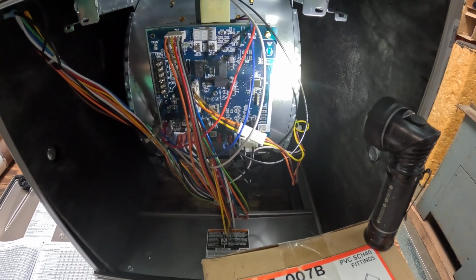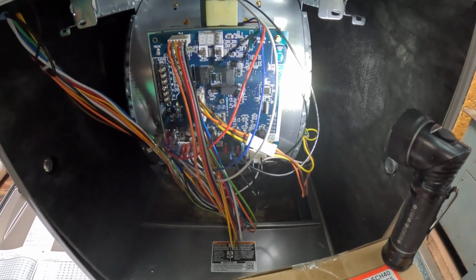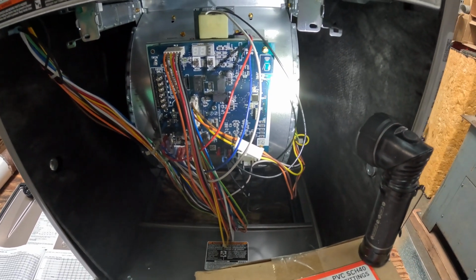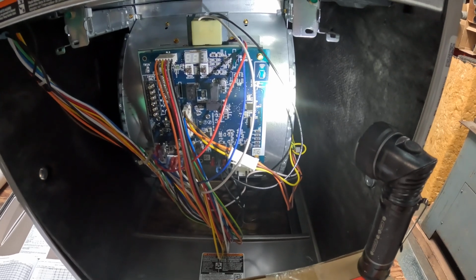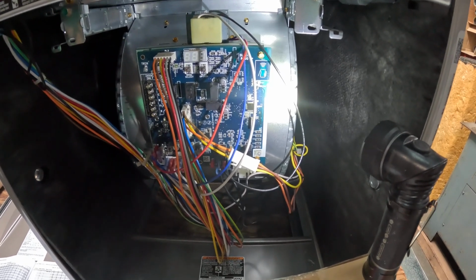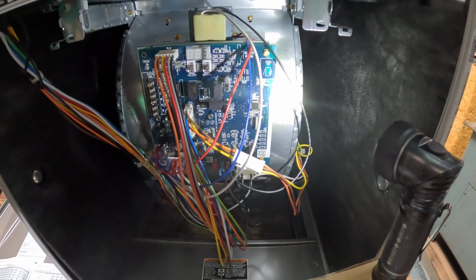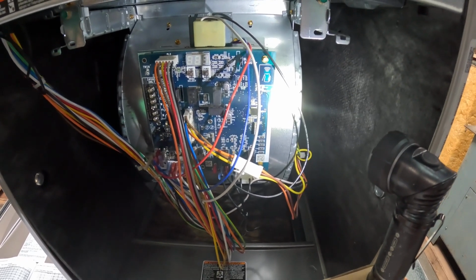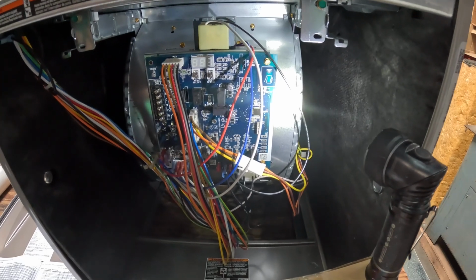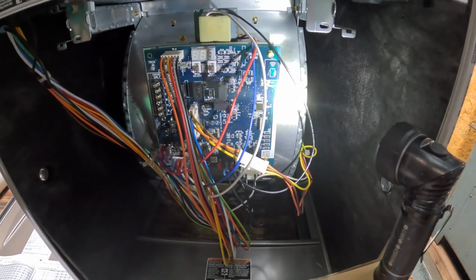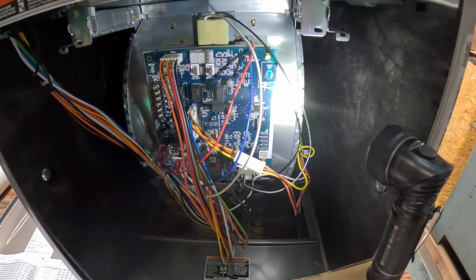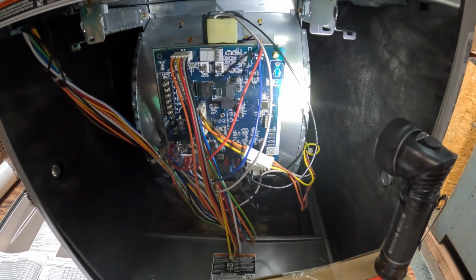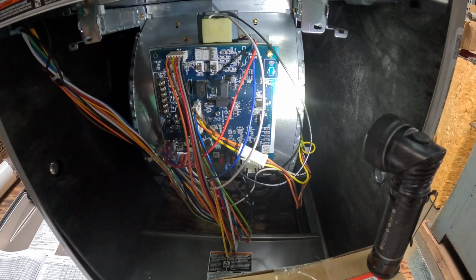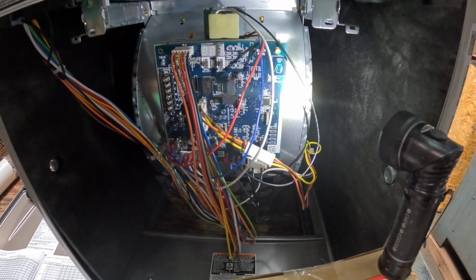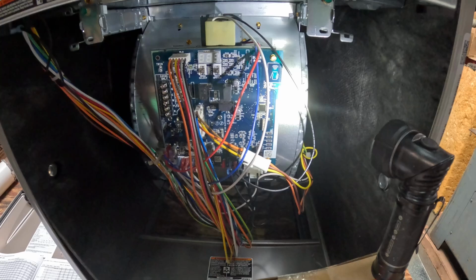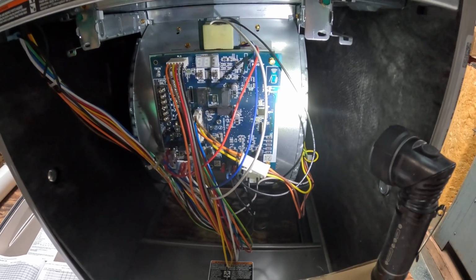These boards have been out for about a year now. We've been doing them for about that long. I thought it would be nice to make a video for people so they can see the process of this. There are a lot of options within those settings. So if you install a larger furnace than needed, you can move down the airflow settings to adjust to your ductwork, so you're not going to have too high a static on the system. It will perform properly. Also for noise, with the blower operation, you can move the CFMs up and down on cooling, heating, and constant fan. So the customer has a very good experience with your install, and they're happy with their system.